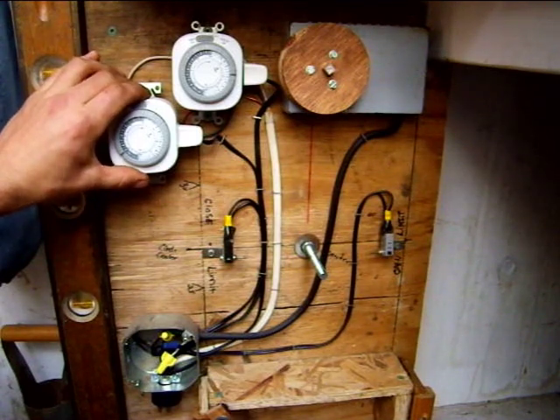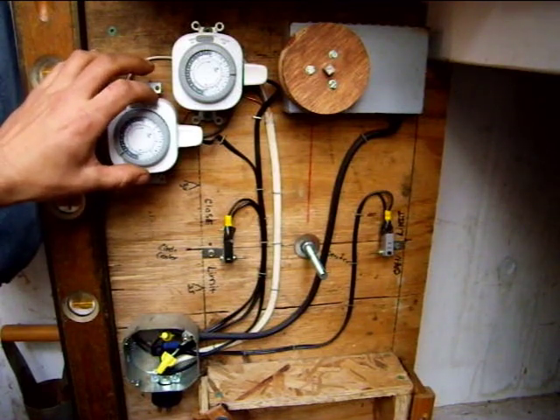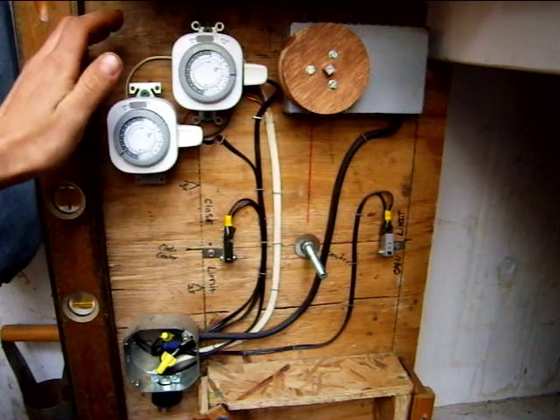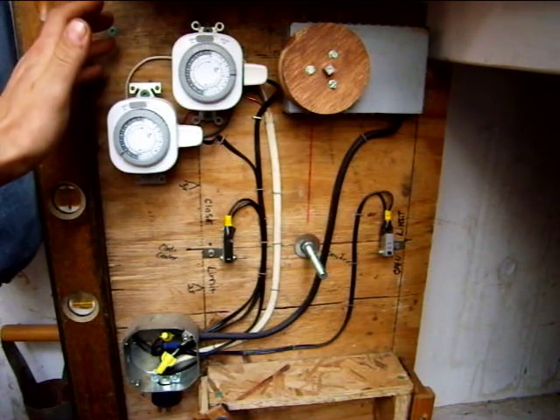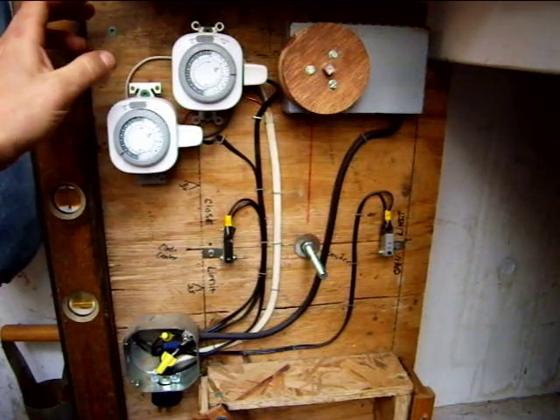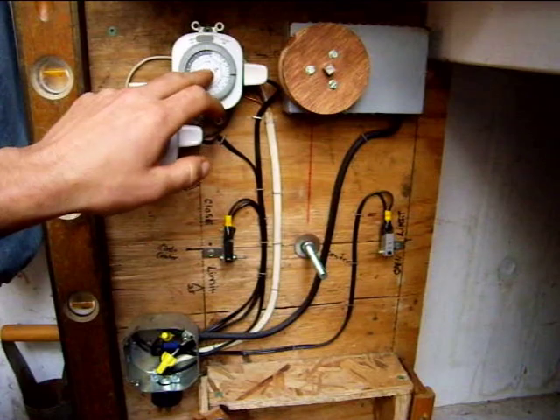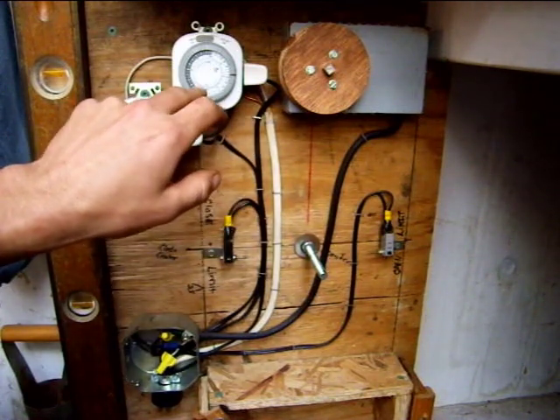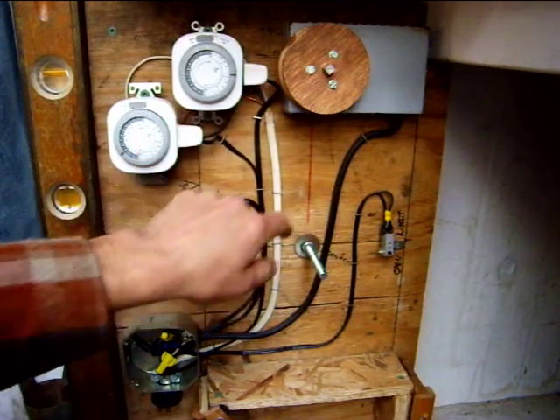So the timers only go down to 15 minutes a piece. So they have to at least be offset by 15 minutes, or they'll both be on and the door will just keep going up and down. But since it's offset by more than 15 minutes, it energizes. The other one's not on, so there's no circuit there even though I have two wires tied into the motor.